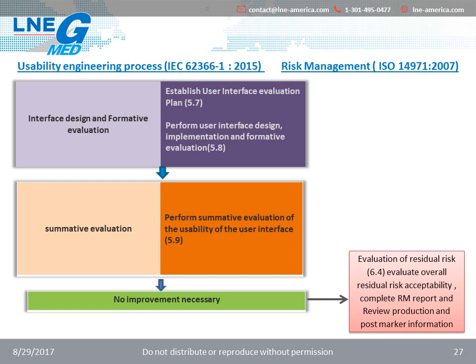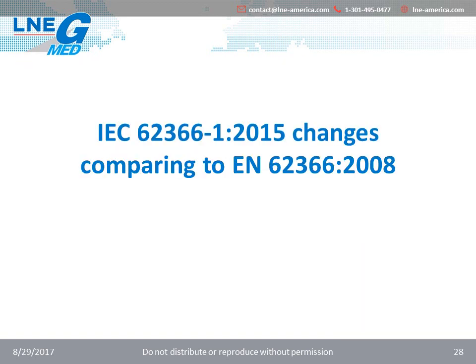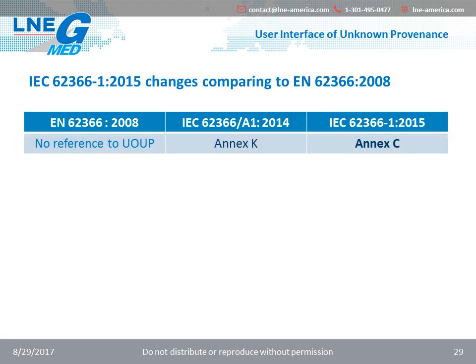Now, if the manufacturer complies with the usability engineering process as described in this standard, then the usability of the medical device as it relates to safety is presumed to be acceptable. Now let's talk about the changes in Part 1 of IEC 62366 2015 compared to Harmonized Standard EN 62366 2008.